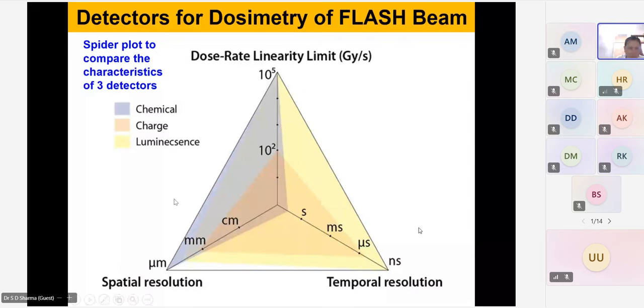If I talk about chemical dosimeters, ionometric dosimeters, which are charge sensitive dosimeters, and luminescence dosimeters, then what we observe is that chemical dosimeters will definitely give good spatial resolution, but the temporal resolution may not be good. Ion chamber based systems will also not give very good results. If we depend on luminescence systems, a larger area of this spider plot is covered by yellow shade. So luminescence systems are thought to be very good. So newer OSLDs or newer TLDs are thought to be a good choice for the dosimetry of flash radiotherapy systems.